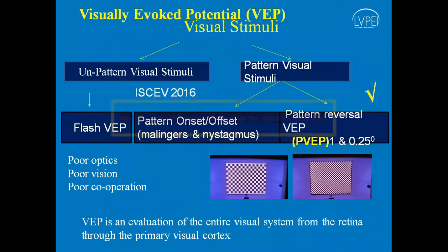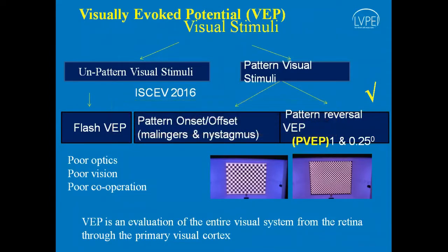So when we are comparing any data, any result, one needs to compare with what is expected for that laboratory and for that setup, which is called normative data. The laboratory needs to generate the normative data for each test, say for ERG, EOG, multifocal ERG, pattern ERG, for a specific age range, for a specific type of recording protocol, contact lens, and the specific machine.